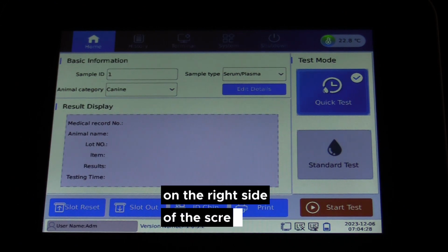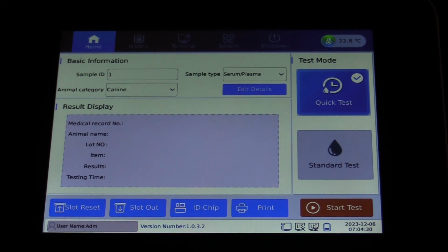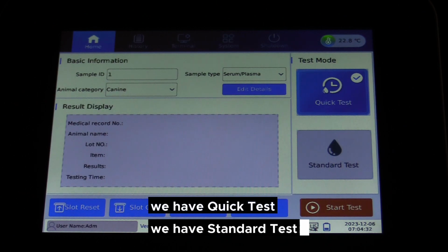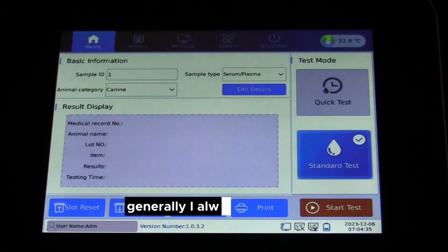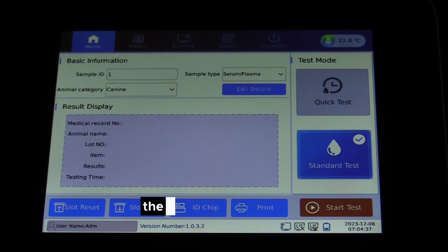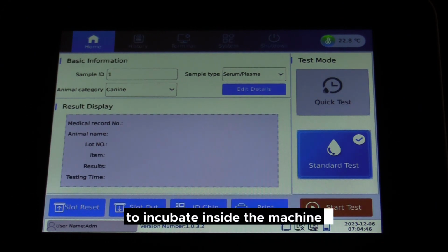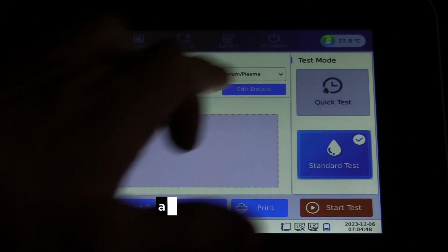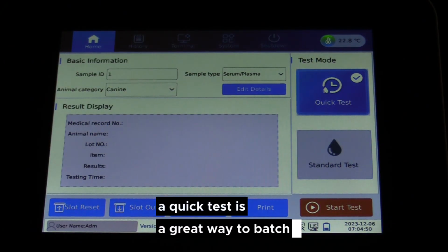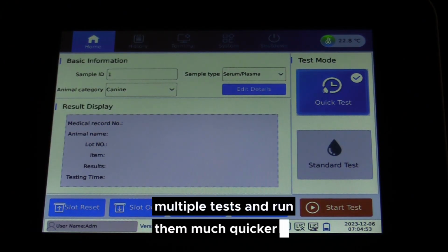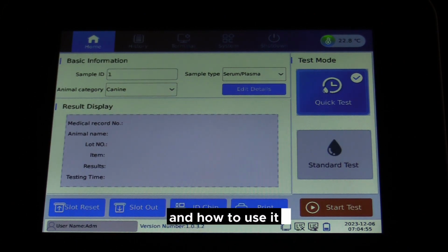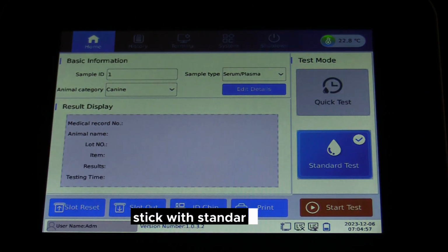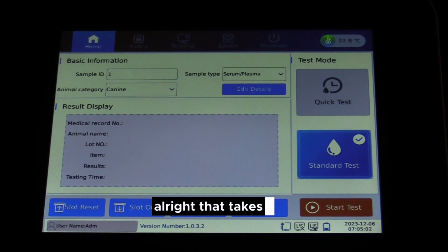On the right side of the screen, you'll see test mode. We have quick test and we have standard test. Generally, I always recommend using standard test. The machine does require a 15-minute incubation time before the test runs. If you're running one test at a time, definitely use standard test. It'll incubate inside the machine. You'll see a timer pop up. But quick test is a great way to batch multiple tests and run them much quicker. And I'll go through that in a little bit here on how to use it, but generally, stick with standard test here. All right, that takes care of the home page.